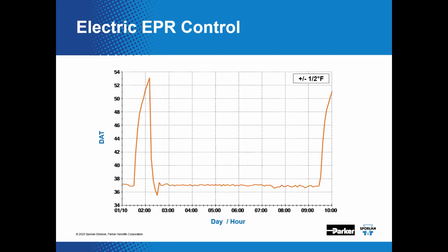This is the log of data that was acquired on a system with an electric evaporator pressure regulator. It was a medium temp system. Again, this graph displays case temperature, discharge air versus time. Set point here was around 37 degrees. As you can see, this is pretty similar to the other version. It's going to vary about plus or minus a half a degree over time. Again, it tracks the set point nicely and recovers quickly after a defrost cycle. Another very efficient way of controlling. And very effective.